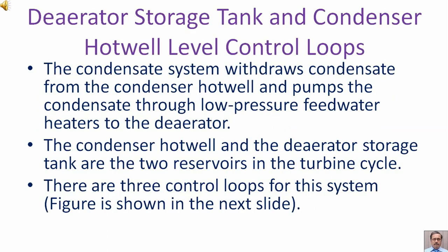The condensate system withdraws condensate from the condenser hot well and pumps the condensate through low pressure feed water heaters to the deaerator. The condenser hot well and deaerator storage tank are the two reservoirs in the turbine cycle. There are three control loops for this system. The figure is shown in the next slide.